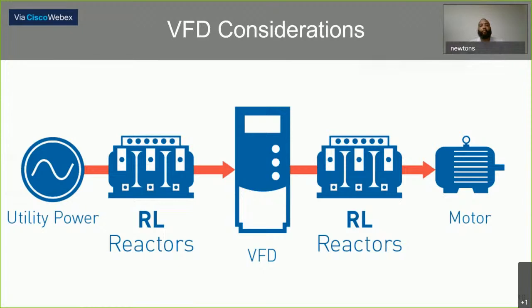So there are some considerations when you decide to install VFDs, variable frequency drives, into your plants, into your applications. This picture is a nice graphic provided by MTE, and it shows you basically, for a power system and the scope of this presentation, where your utility feeds you power. Most cases it's 480 that we're dealing with. On the input side of the drive, we're showing a line reactor. Then we're showing a drive, and then to the right of that drive, we're showing another reactor, which in this case we're calling an output reactor or a load reactor. And then finally we get to the motor. Throughout the next couple slides, we're going to talk about why and when to install these devices, amongst other things.